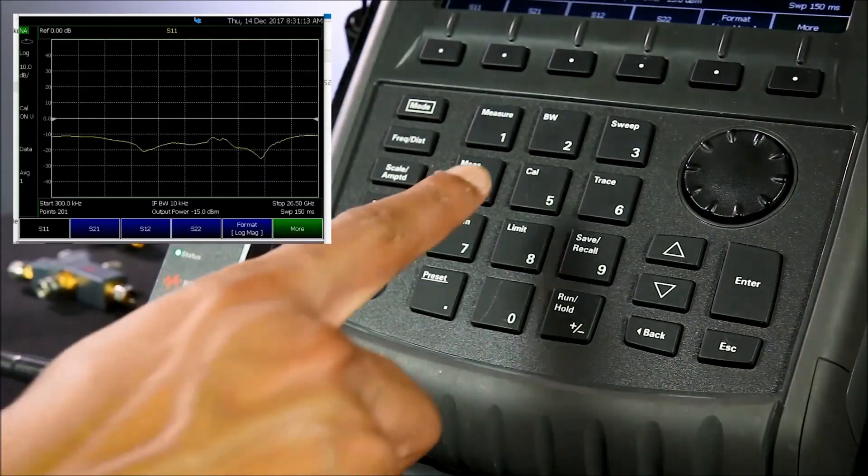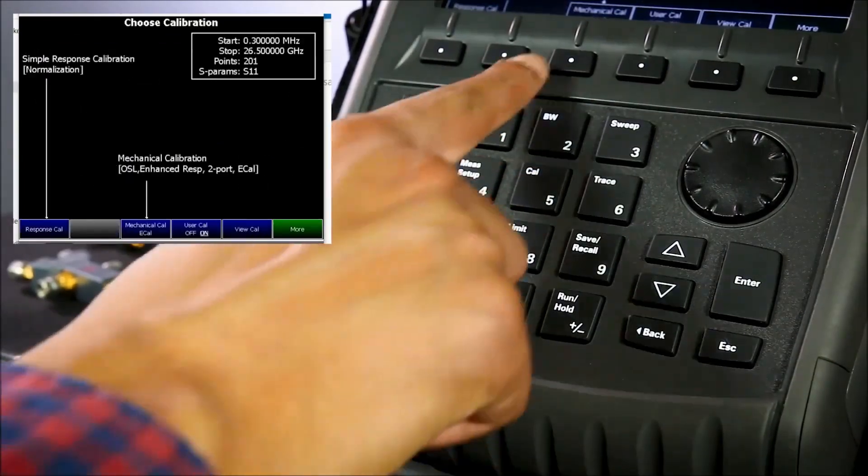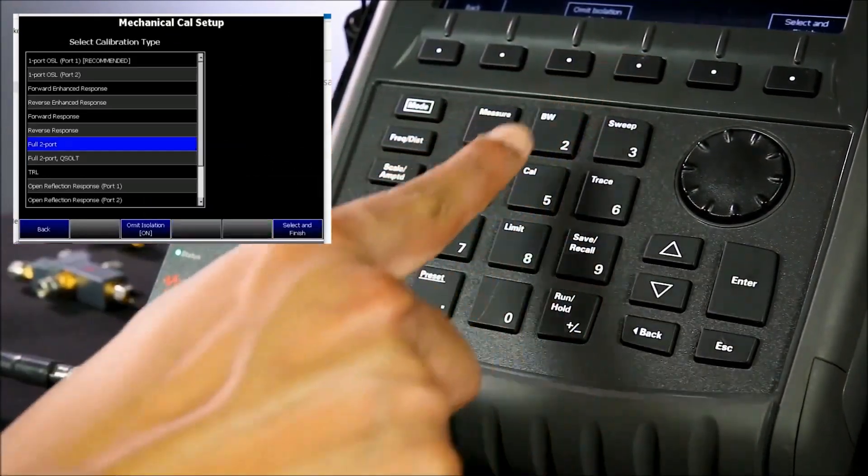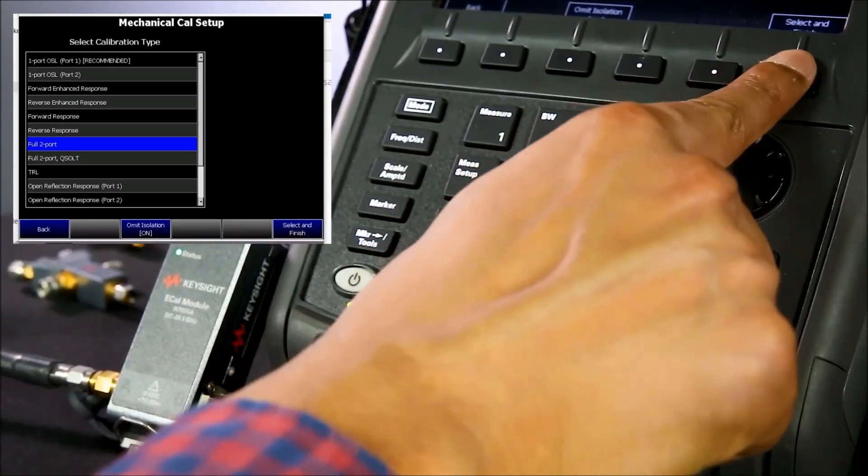Under the FieldFox calibration menu, select the mechanical CAL e-CAL. Under change CAL type, I will select a full two port CAL, and then select and finish.